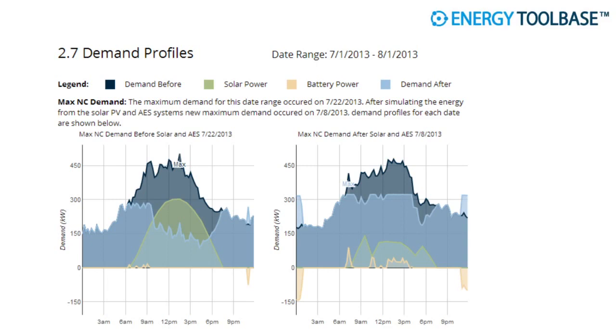Now we have solar sitting on top of a commercial building, providing demand electricity, and a battery that only runs for a very small amount of storage, maybe 3 or 4% of the total facility's energy use for the day, or maybe even less than that. But we're not trying to do the entire electric bill of the building. We're just trying to shave off the peak in a cost effective manner. What's even more interesting is if the client didn't have budget for this large of a system, just focusing on the very peak can be even more cost effective.